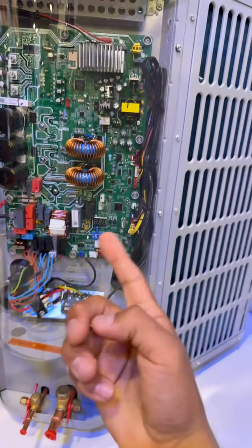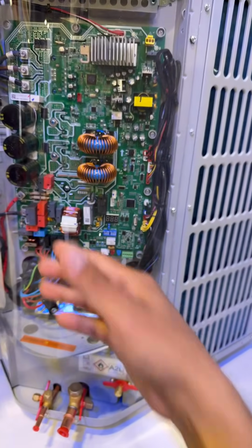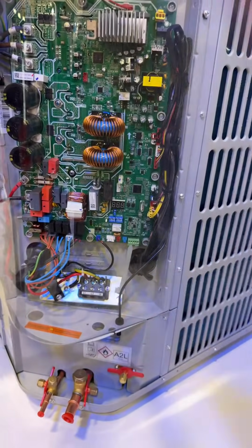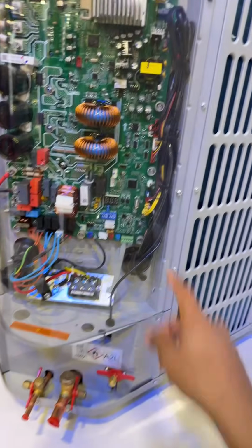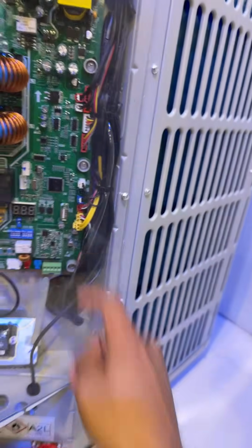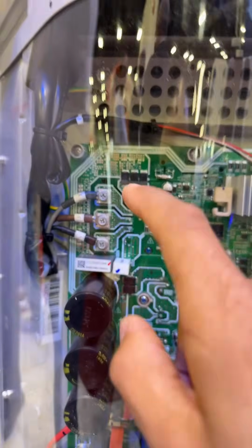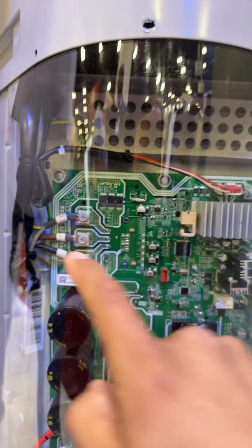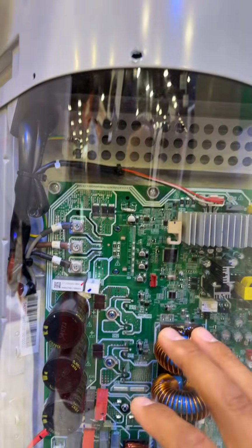Speed up the condenser fan or the indoor fan. That's all we're doing, that's all inverter technology is, guys, we're using thermistors. So the first thing I would do when checking a board that's not working is ohm out the thermistors, for inverter compressors that take inverter technology.